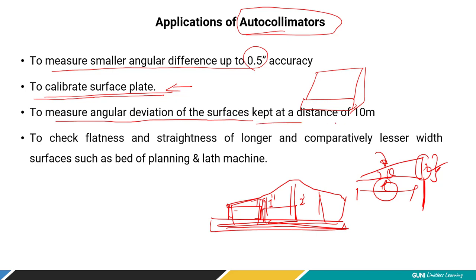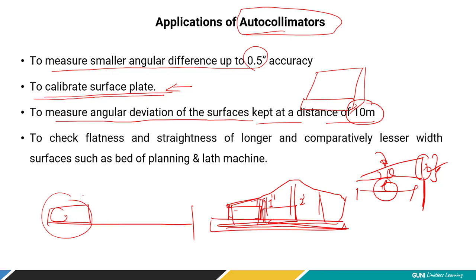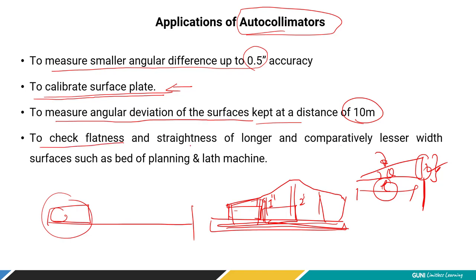The autocollimator can also measure the angular deviation of a surface kept at a distance of up to 10 meters. This is an advantage: the device is simple and portable — you can put it on a table, and even if the object is far away up to 10 meters, you can still take its measurement. It is also used to check flatness and straightness.